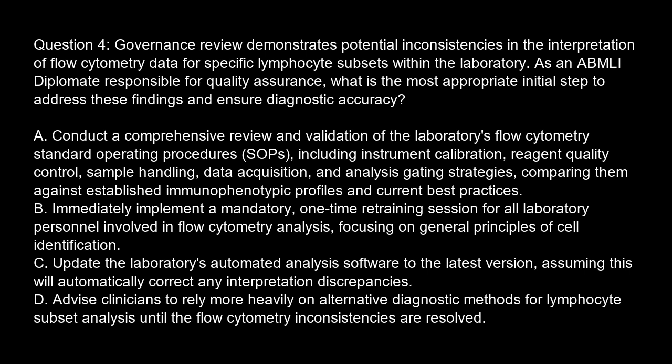Conduct a comprehensive review and validation of the laboratory's flow cytometry standard operating procedures, SOP, including instrument calibration, reagent quality control, sample handling, data acquisition, and analysis gating strategies, comparing them against established immunophenotypic profiles and current best practices.